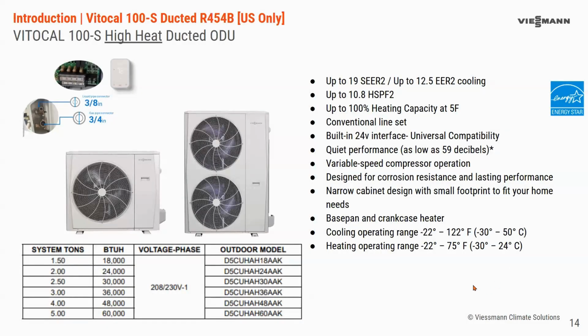And then we have the high heat. So really what this is, is a boost in efficiency, and your capacity at 5 degrees is greatly increased. So between 30+% more than what you get with the standard heat. Same conventional line set, 24-volt interface, variable speed compressor, all that's the same. The difference is the performance and the internals that allow it to get that higher capacity at 5 degrees, and the operating range down to -22.